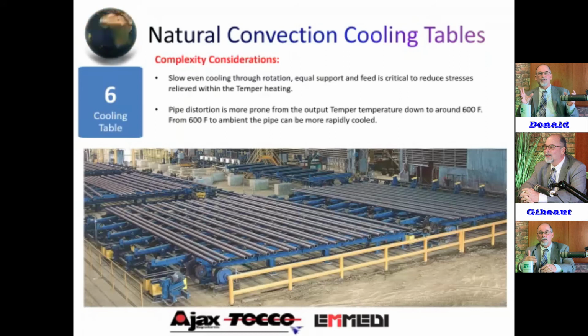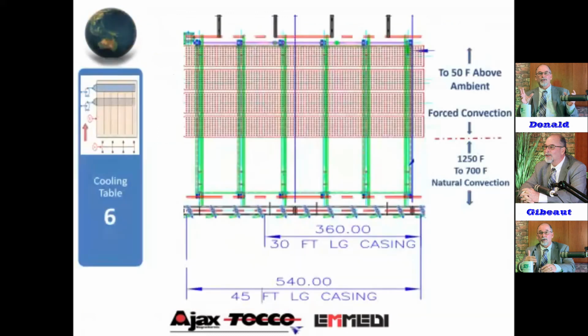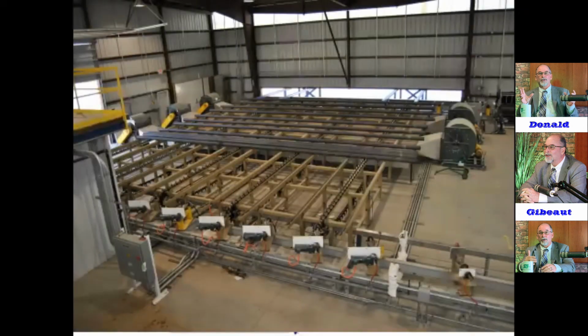Just air cooled. And we showed our forced air convection fans to help that. And here's a picture of it. And this shows where we naturally convection cool down to 700 degrees, which is actually the spec. We like a little buffer there, so we designed for 600 degrees. But after that, if we're fitting into an existing building, we can pour the coals to it with these forced air convection fans and fit a higher tonnage line in a smaller existing building.